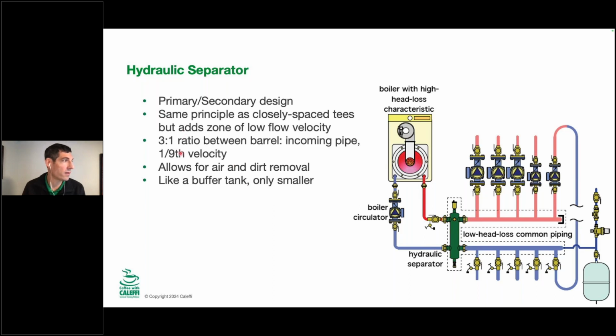So one of the reasons that this 3-to-1 ratio works well, for a couple other things that we'll talk about, is you're going to have a 1/9 velocity inside of that chamber. So it really calms down the flow, and that helps for the air and dirt separation as well, which I'll get into towards the end. So this is the smallest version of a buffer tank that will still work for primary secondary piping, is kind of what we're doing here.